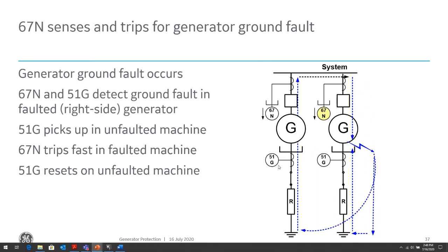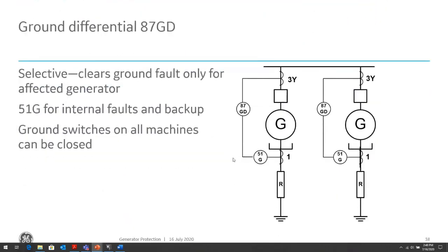So the 67N and 51G will detect the generator ground fault. The 51G will pick up for faults in either zone of protection, whereas the 67N will only pick up for faults within its zone of protection, to provide that discrimination. The generator ground differential is the same as the phase differential. It's discriminatory by default because it will only operate for faults within its differential zone, because of the current in equals current out principle.